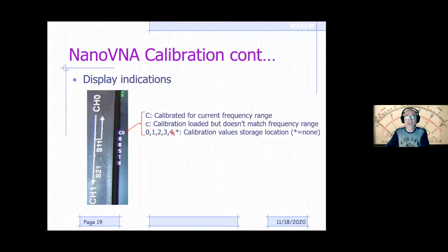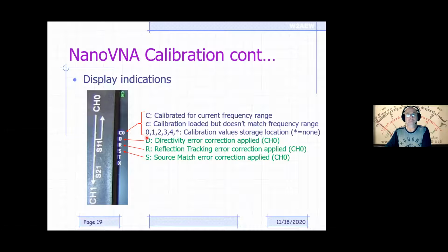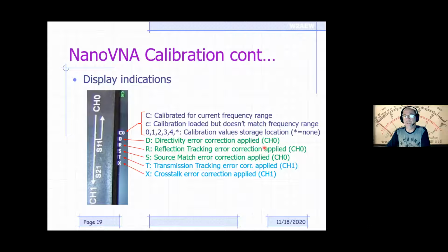Okay. One thing that's handy on the VNAs for most of them, any calibration that you store in slot 0 gets recalled when you power the unit up. Okay, so it's kind of a default power up condition. These other letters, if you will, or digits, refer to directivity, reflection, and source match errors. So this says that you've done the calibration and the error correction for those things is being applied. These generally all apply to channel 0. These are all applied to essentially reflection-based measurements. The T and the X stand for the transmission and crosstalk corrections being applied. So when you run through the full 2-port calibration, all of these letters will show up.